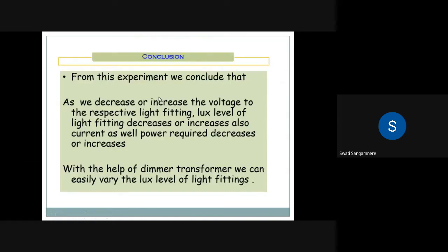Okay, then the conclusion. From this experiment, we conclude that as we decrease or increase the voltage to the respective light fittings, the lux level of the light fitting decreases or increases. Also, current as well as power required decreases or increases. So, with the help of a dimmer transformer, we can easily vary the lux level of light fittings. So, this is a very simple technique to control the lux level.